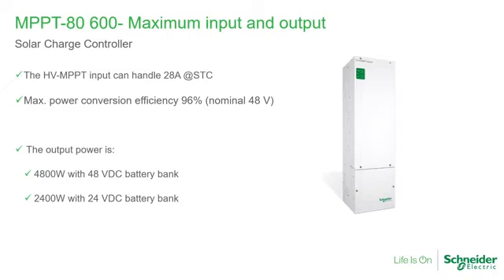Remember when we first started talking about this product, I compared it with a grid tie inverter in the sense of the 600 volt stringing of modules. But there's another thing that we do with grid tie inverters, which is very common in the industry, which is oversizing the array. And there's many reasons why we oversize the array. Maybe the orientation of the array is not ideal. We are also having to accommodate for losses of the modules throughout the life expectancy. So it's very typical for an array to be oversized by 20, 25%. I've seen arrays oversized more than that in northern hemispheres where solar irradiation is not optimum.